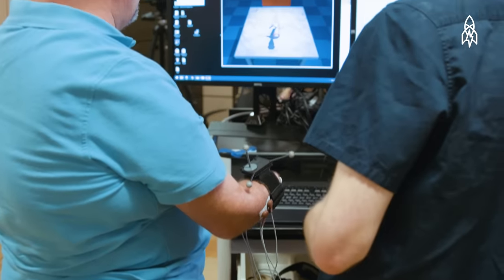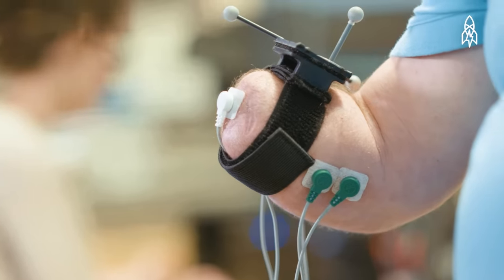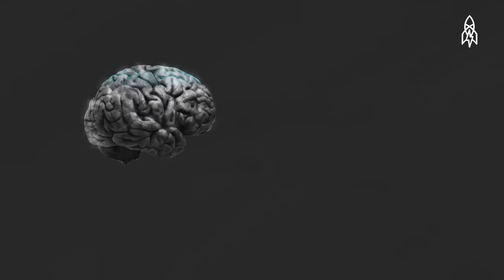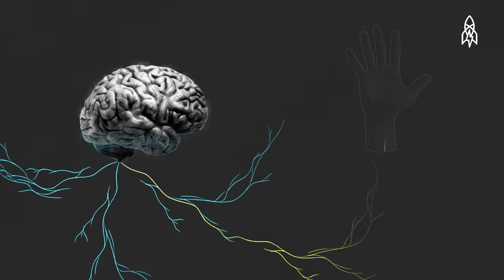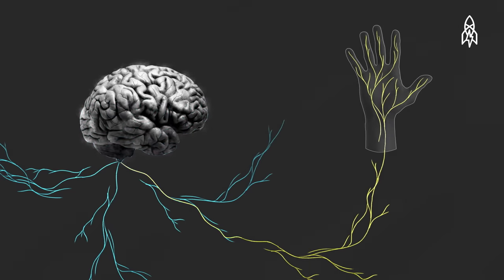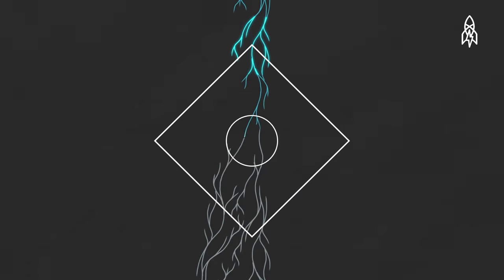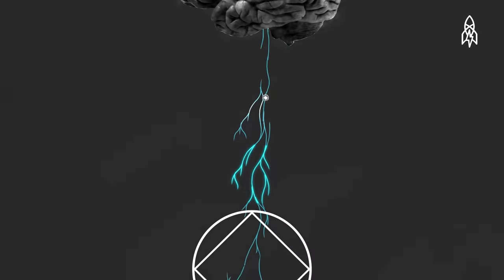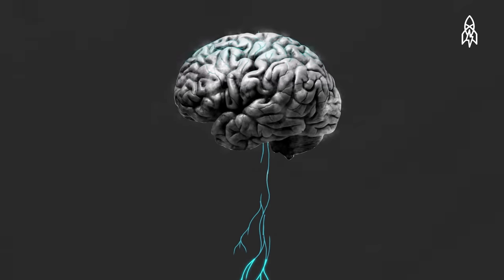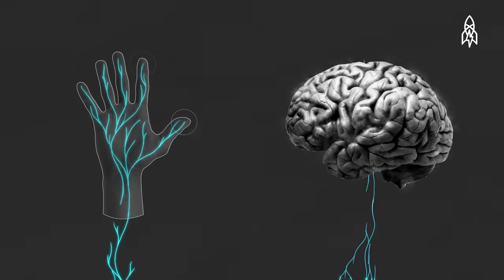The research that we've been doing is reconnecting the man to the machine — basically learning how to take what the prosthesis feels and translate it so that the person using it feels it. For the brain to feel touch as being their actual hand, it's really important that we activate or stimulate the wires that the brain always used to get from the hand. We implant cuff electrodes and then apply really tiny amounts of current that activate those wires, and that information then goes to the brain. So we've been learning how to place this information on that nerve so the brain thinks it's his hand.